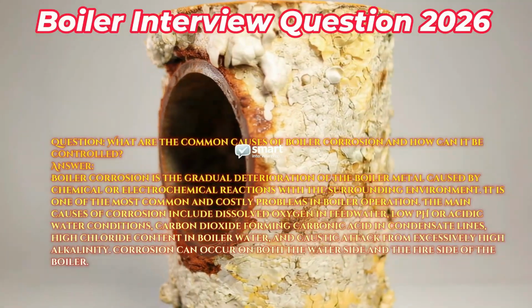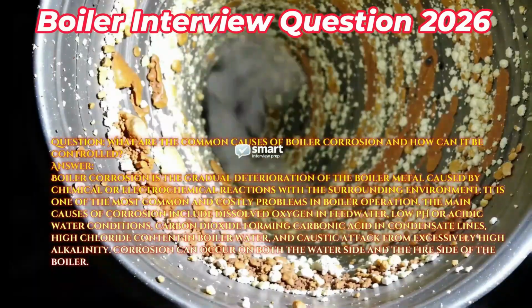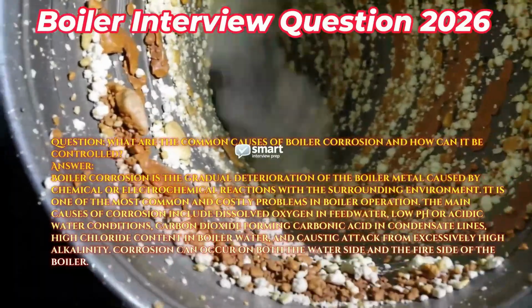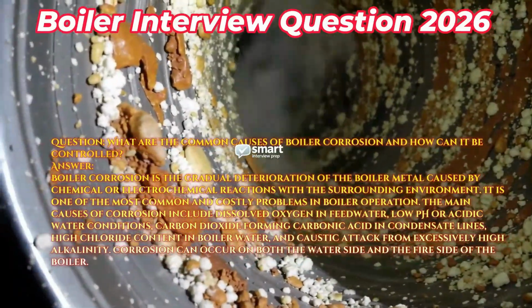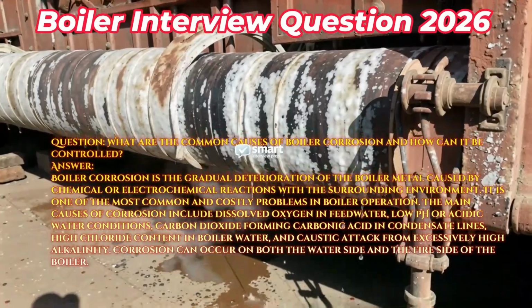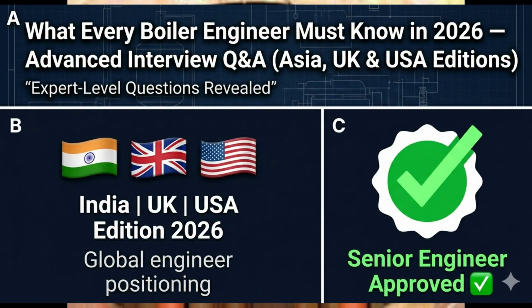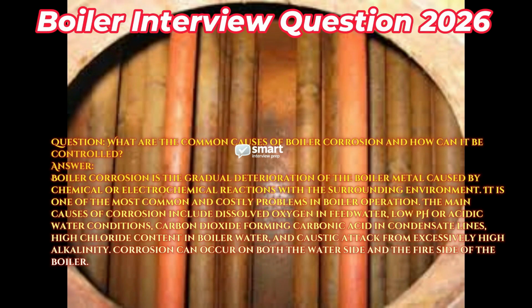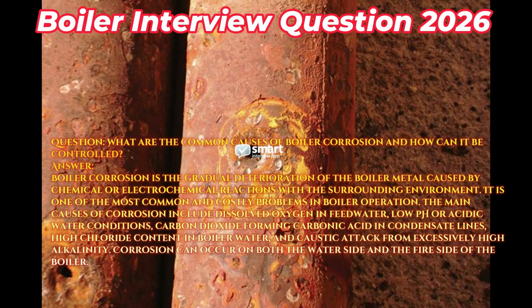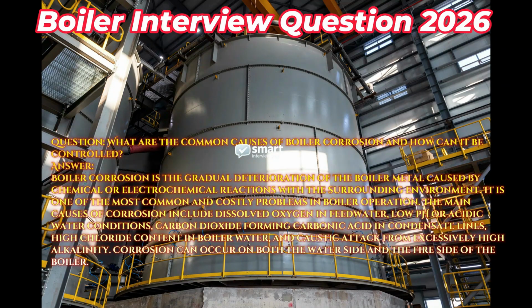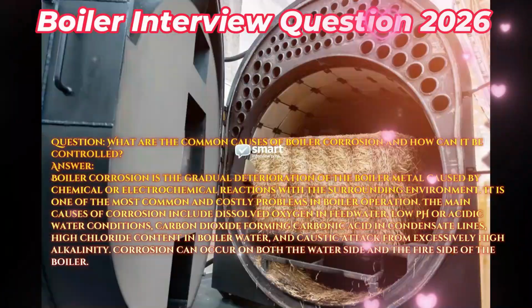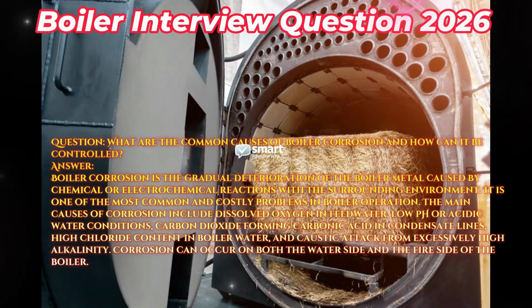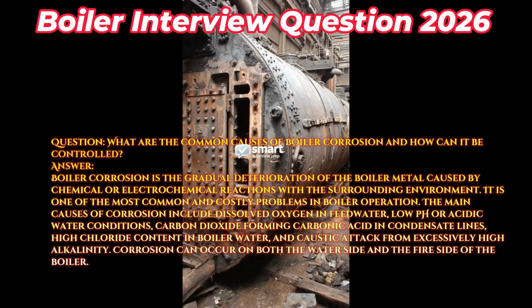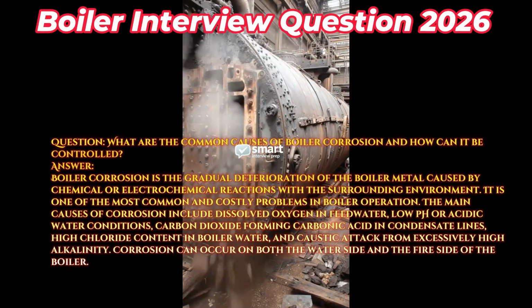Question: what are the common causes of boiler corrosion and how can it be controlled? Answer: boiler corrosion is the gradual deterioration of the boiler metal caused by chemical or electrochemical reactions with the surrounding environment. It is one of the most common and costly problems in boiler operation. The main causes of corrosion include dissolved oxygen in feed water, low pH or acidic water conditions, carbon dioxide forming carbonic acid in condensate lines, high chloride content in boiler water, and caustic attack from excessively high alkalinity. Corrosion can occur on both the water side and the fire side of the boiler.